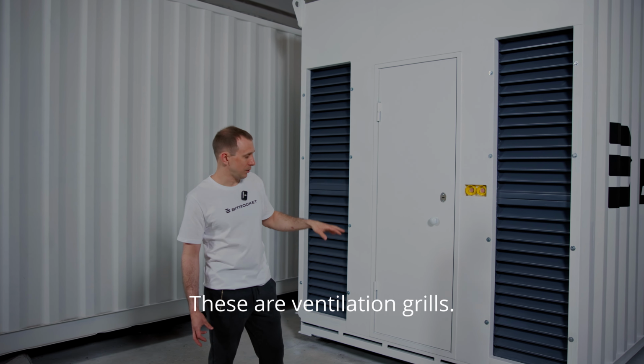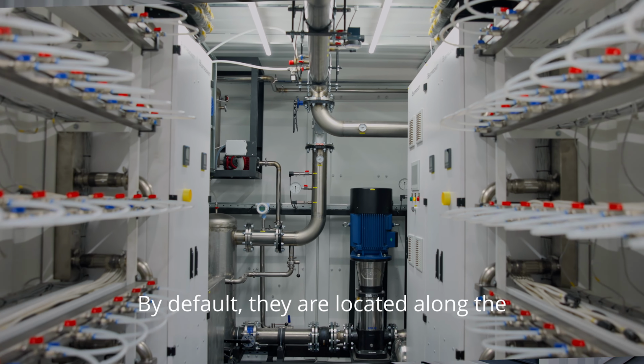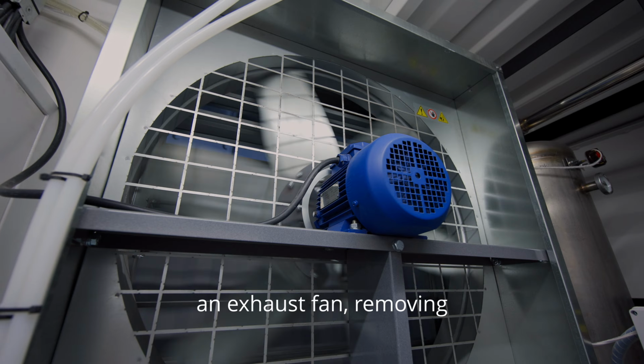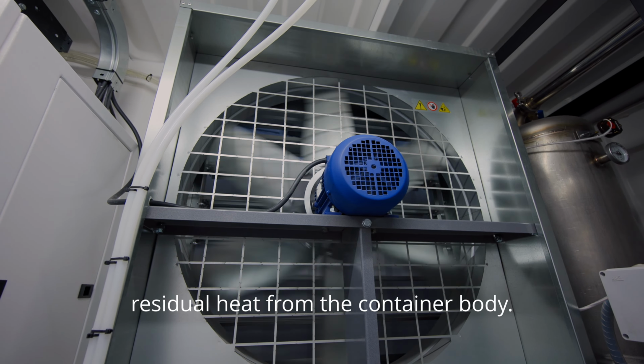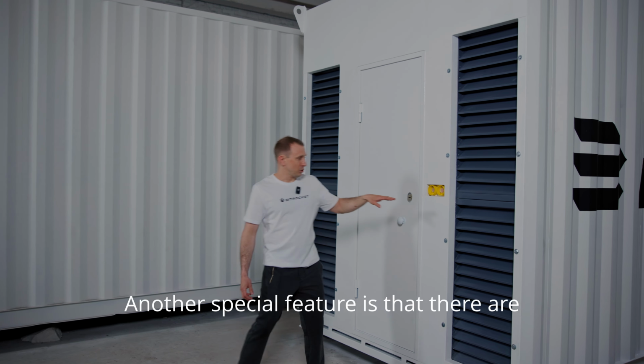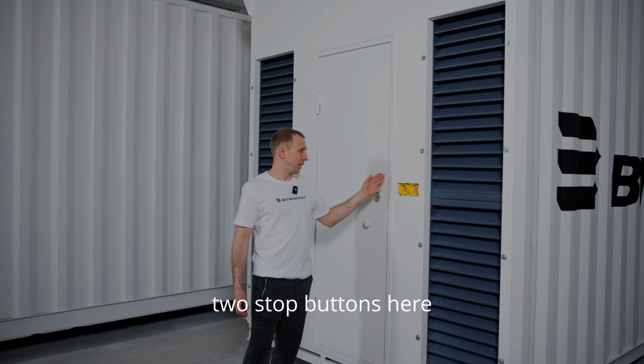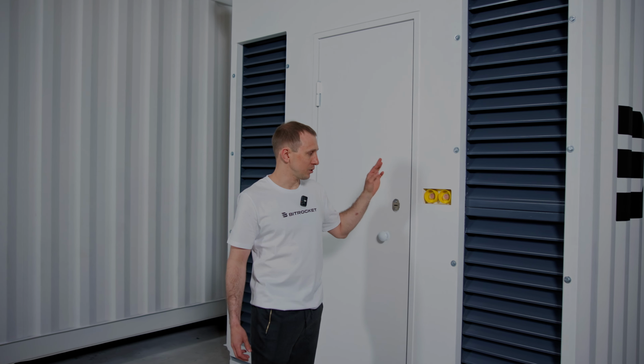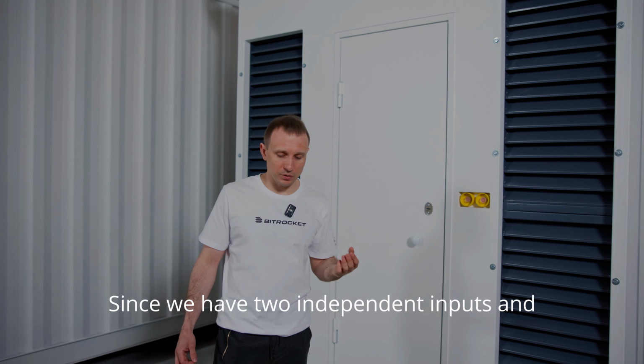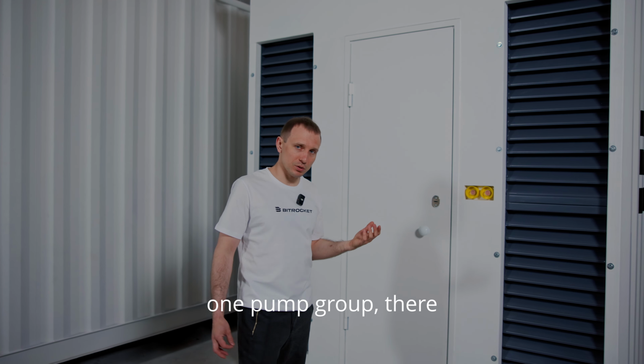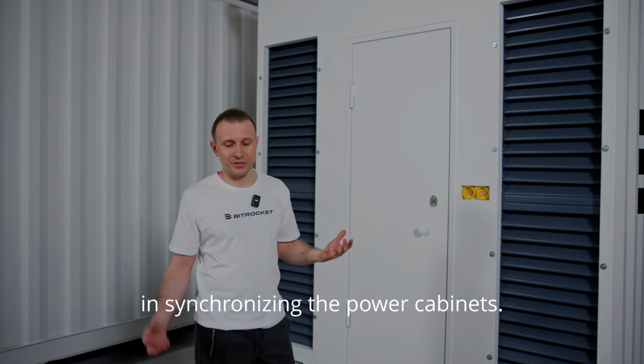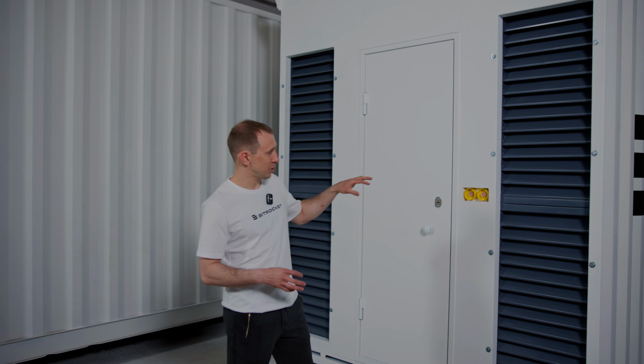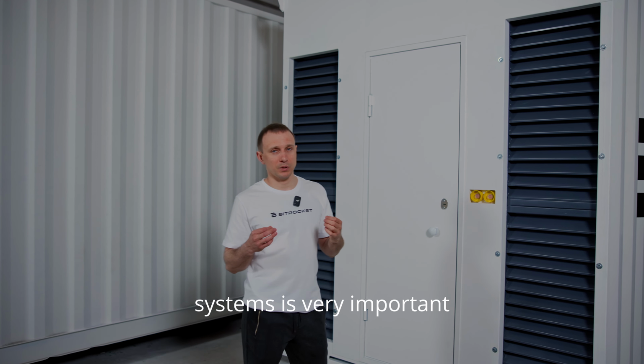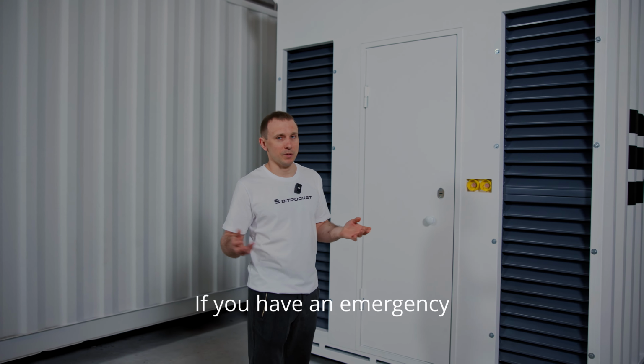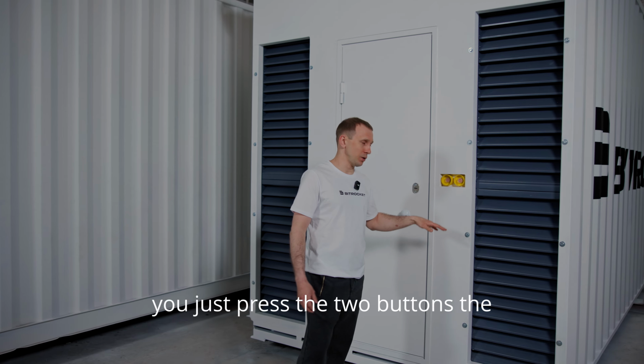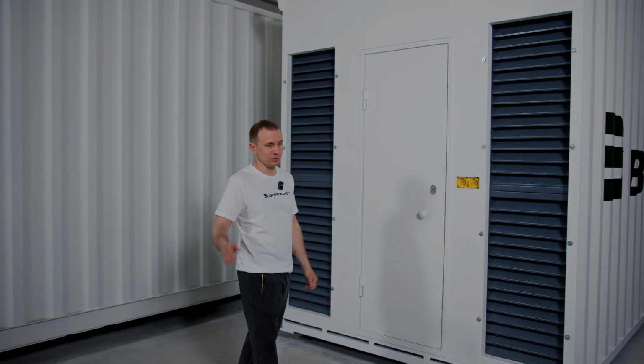Next, these are ventilation grills. By default, they are located along the racks and are blown by an exhaust fan, removing residual heat from the container body. Another special feature is that there are two stop buttons here, for the left and right switch gears. Since we have two independent inputs and one pump group, there are certain difficulties in synchronizing the power cabinets. So we had to make two buttons here, since the galvanic isolation of these systems is very important. If you have an emergency, you just press the two buttons, the switchgear turns off, and you're fine.